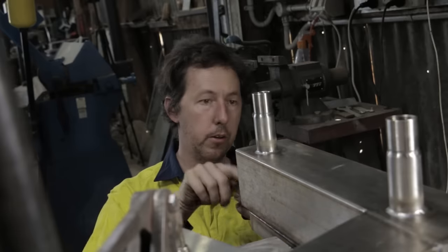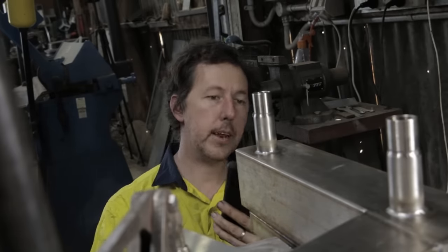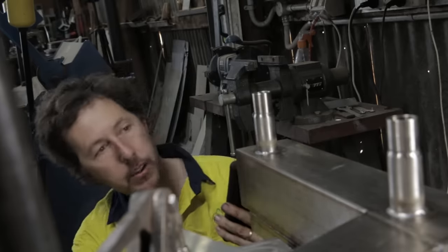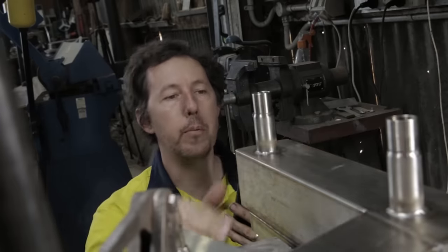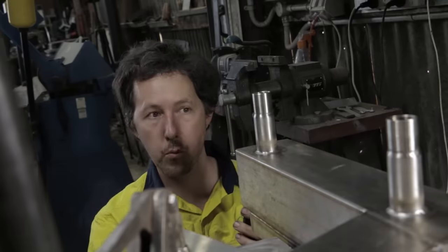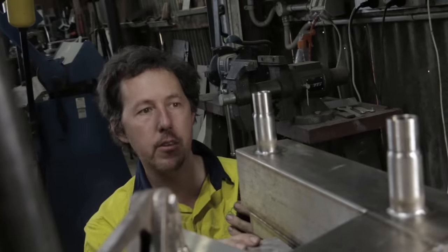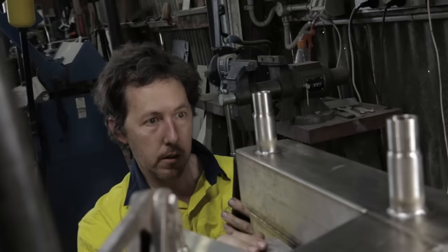So, got to check on the inside as well and the outside. So far, so good. I can't see any water, so I'm going to call that watertight. Ideally, you could also do this test with compressed air and some soapy water, which would be the more proper way of testing the airtight or watertight nature of a vessel. But this will do.